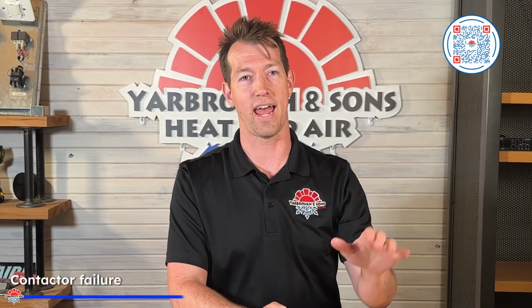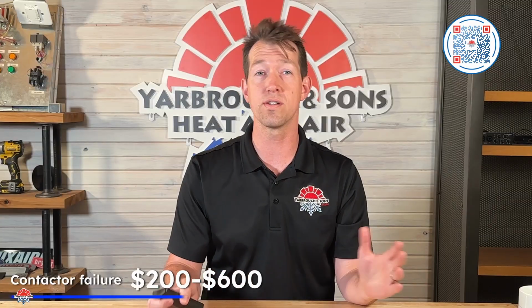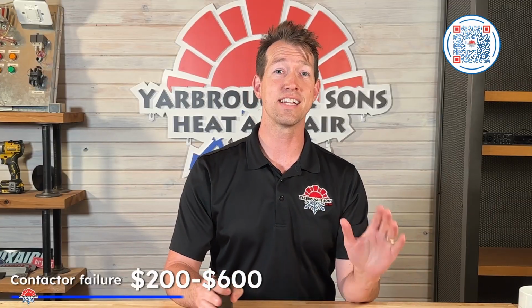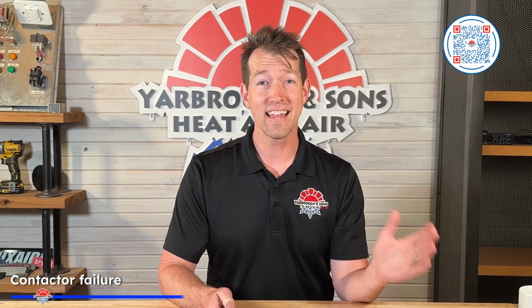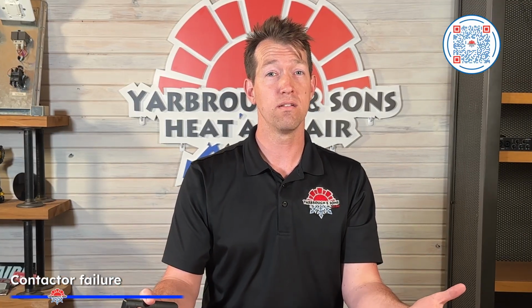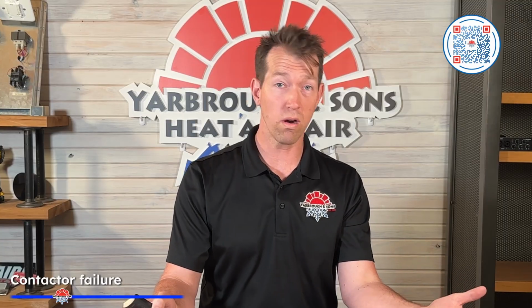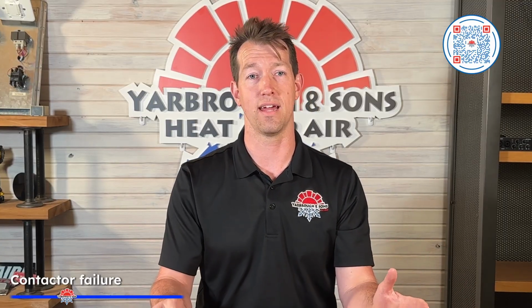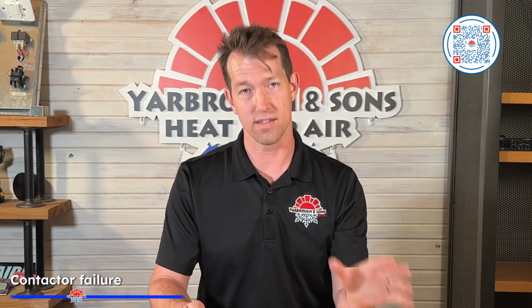Moving on. I'm setting that aside. We're moving on to contactor failure, okay? Contactor failure runs somewhere between $200 to $600. The contactor is the relay switch that controls power to the compressor and the outdoor fan motor. In other words, it's really important. And when it fails, and they do, right? They pit and burn over time from the arc of the current switching. The system will either run the outdoor unit or not at all, or it'll chatter and cycle repeatedly. If your air conditioner sounds like it's having a really fast conversation, that's not a good thing.